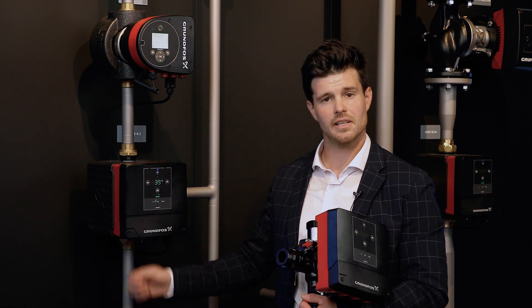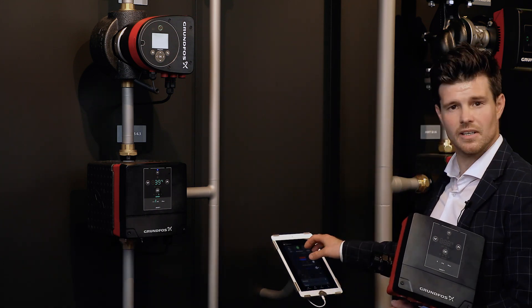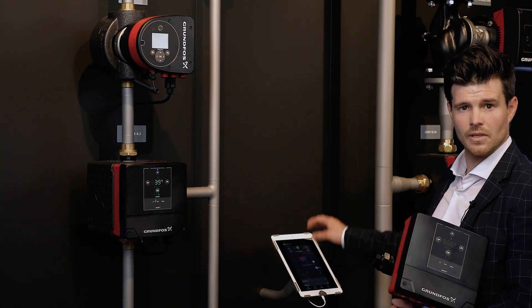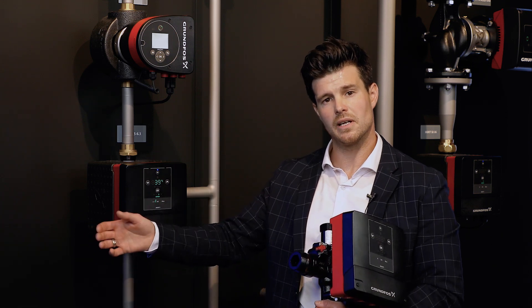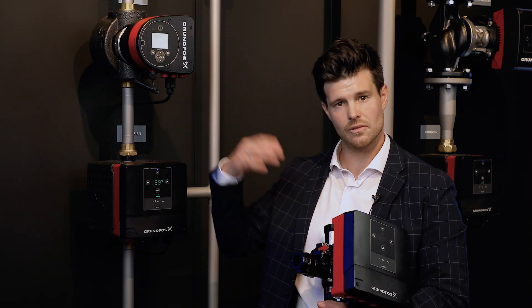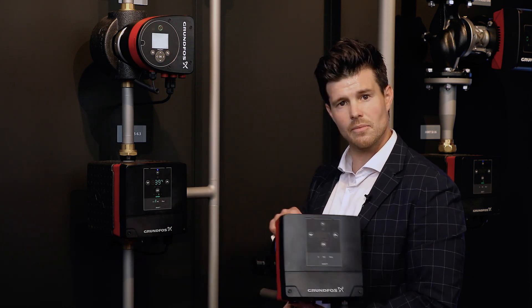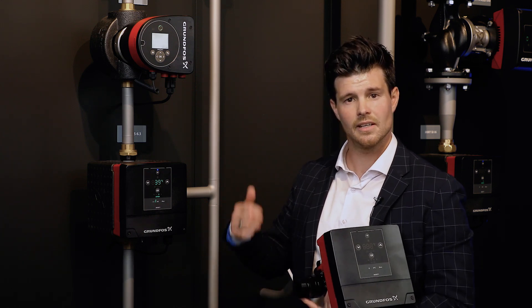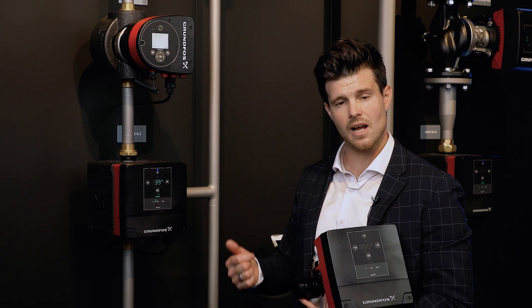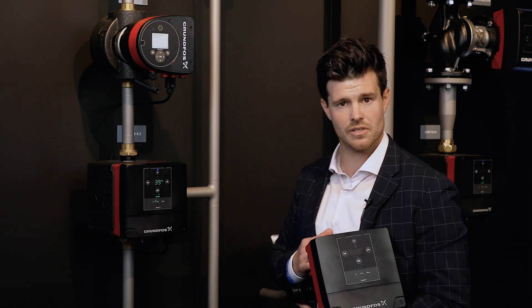There's an Ethernet port on the unit. Connect it to the internet and follow a user-friendly wizard on Go Remote, which gives you a number for your specific mixing unit. Then go to Building Connect, enter the number, claim your Mixit device, create a location, put it on a map, and monitor it for free. If you want remote control, trend data, analytics, insightful alarms, and user management, you can upgrade from the free tier to a professional license.